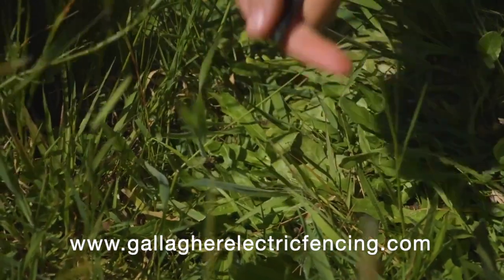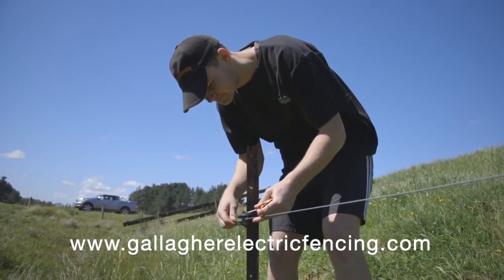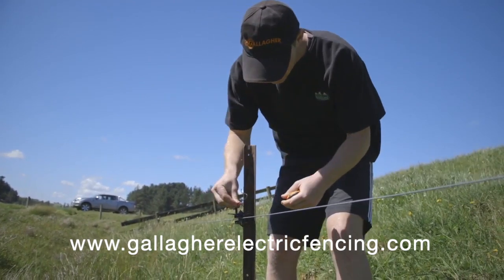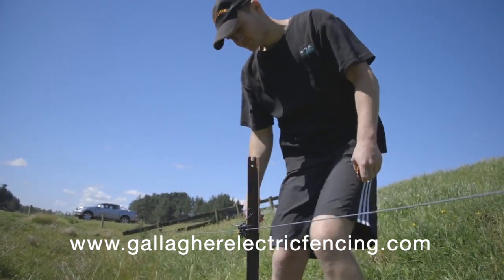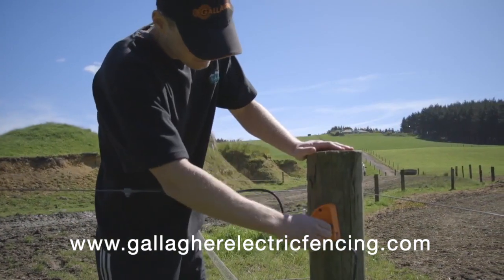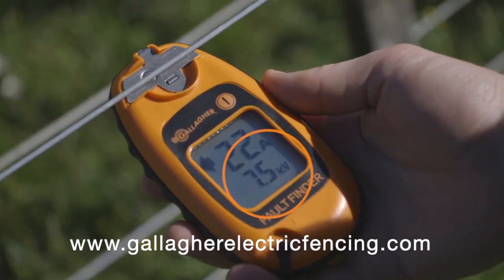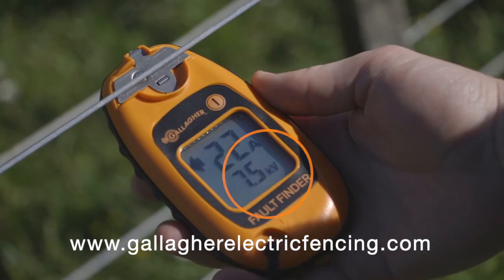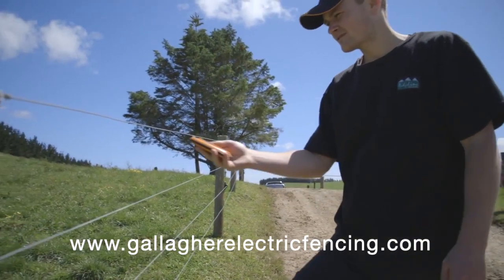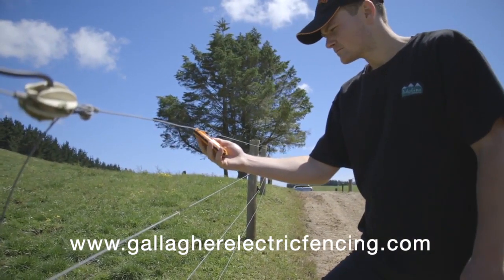When the repair is complete, the power can be turned back on via the energizer, the cutout switch, or by using the remote. Test the fence and see if the voltage has returned to what is normal on your property for effective performance.